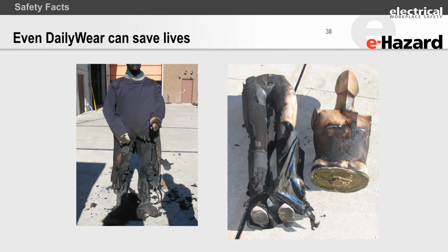I've been on many accident investigations now, over 225. And what I found in those accident investigations, the people who die or get really, really badly burned are wearing non-FR gear and they're near or in the arc flash. Most electricians now know that at certain points when I'm making it safe, when I'm de-energizing, grounding, testing, I need to wear arc-rated gear. But there are a lot of accidents where people, or even supervisors that are supervising but are not officially doing the work but are really nearby.